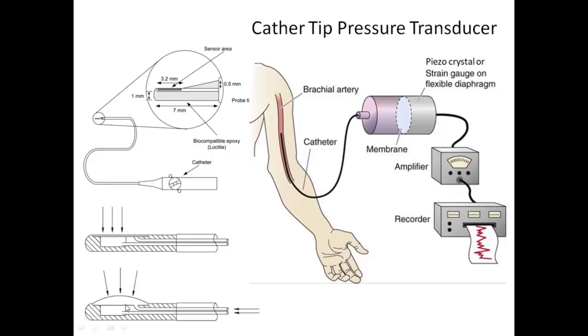Now from here you can see in the third figure, from this site of measurement, when the pressure changes take place, the diaphragm bends. When it is bending over here, the incompressible liquid inside this particular catheter is transferring the pressure from this site of measurement to the sensor that is attached over here. This might be a strain gauge, a piezoelectric crystal, or a capacitive transducer. Over here we can have a sensor. So this pressure will get applied over here, and an electric voltage signal will be generated.